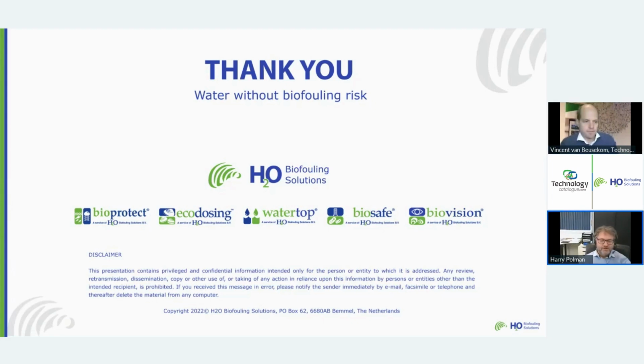Okay, for ecodosing to control biofouling, two numbers are generally important to take into account. The first is what level of biocide you need to prevent biofouling up to the critical point in your cooling water system, generally the heat exchanger condenser. The second is what the discharge level is at that specific location. To control biofouling you need to be efficient up to the inlet of the condenser, but you also have to be in compliance with the discharge limits. So we try to find a balance between the lowest amount of chlorine, or biocide in general, in the cooling water system itself while staying in compliance with the discharge. So far we are capable of finding this balance.